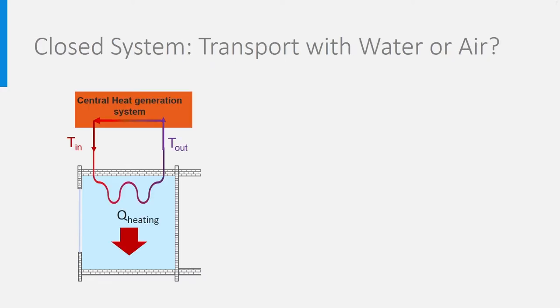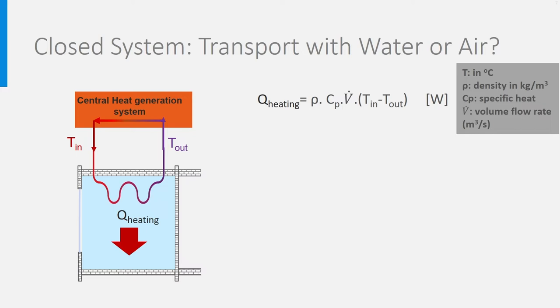To make a choice between water and air as the transport fluid for heat and cold, we need to consider the size of the transport ducts. Let's start with a closed system and consider heating — it works exactly the same for cooling. In a closed system, a fluid is heated by the heat generation system (a boiler, for instance) and circulated through a pipe and a heat exchanger to the room. The fluid gives its heat to the room, heating it, then returns cooled to the heat generation system. The quantity of heat Q_heating is expressed as: Q_heating = ρ × Cp × volume flow rate × (T_in − T_out).